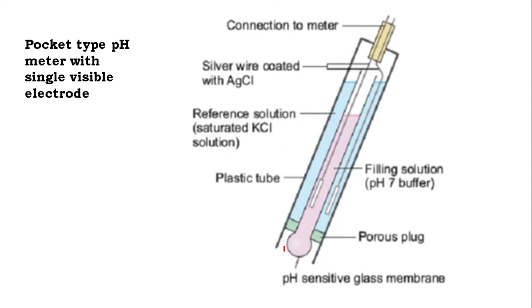Okay, and how are these things working? How does the pH meter work? The potassium chloride inside the glass electrode is in a neutral reference solution with pH 7. So it contains a certain amount of hydrogen ions. You know, even for pH 7, there is a certain amount of hydrogen ions. Only the fact is that it is equal to that of hydroxyl ions. Now, the glass electrode is measuring a difference in pH between the test solution and the reference solution.